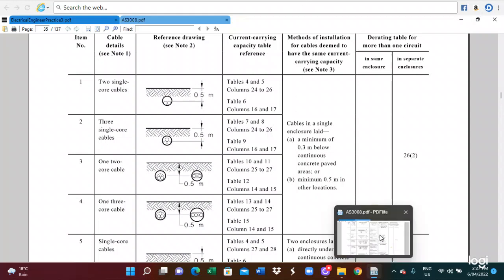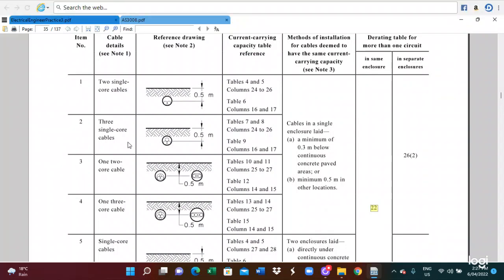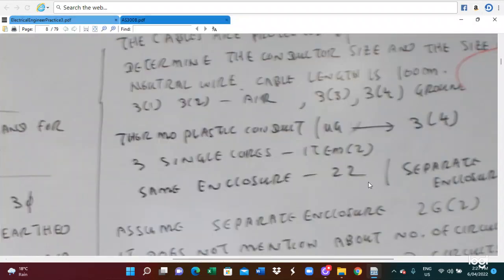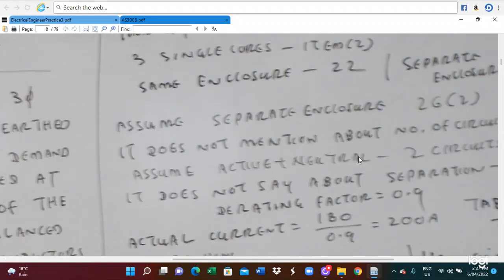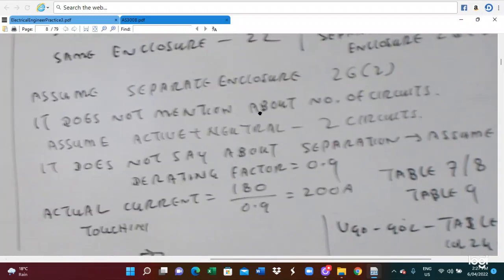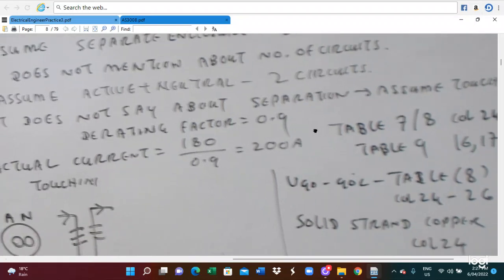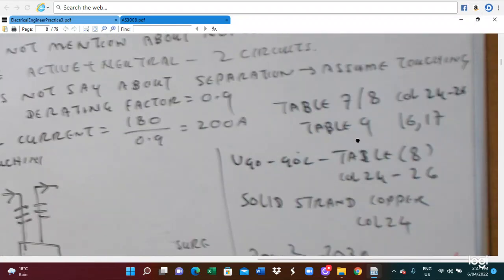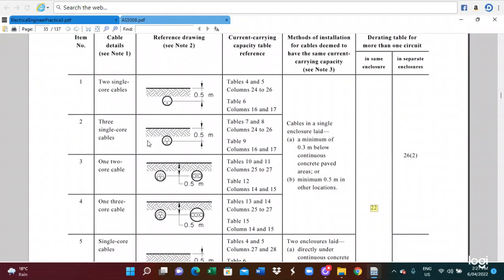So this problem is further referred to another table because of the 3 single core cables. V90 refers to table 8. So there will be tables 7, 8, 9. In this case, V90 means that we have to refer to table 8, column 24 to 26. Yes, table 8, column 24 to 26 needs to be referred, and also table 22. So we look at table 8.